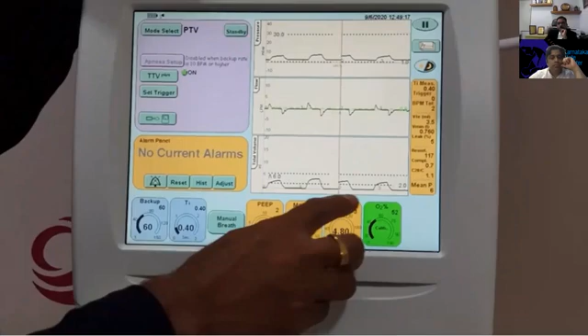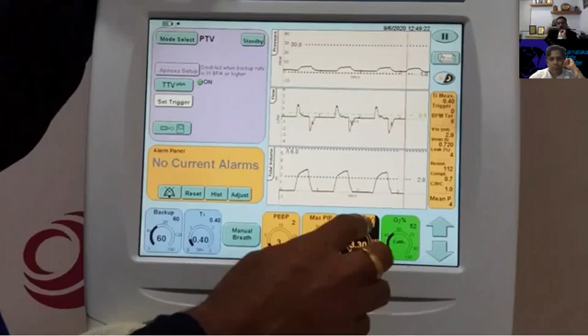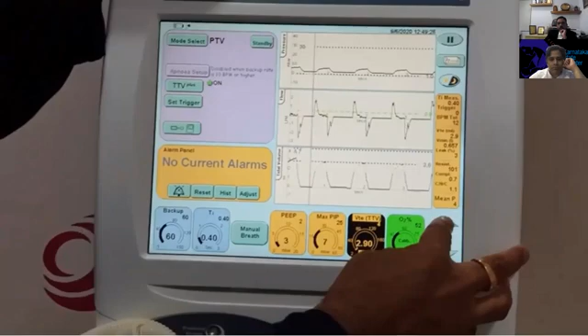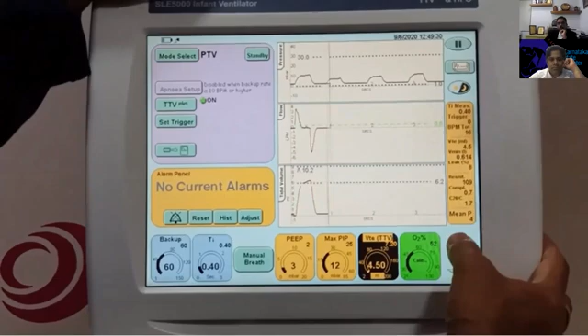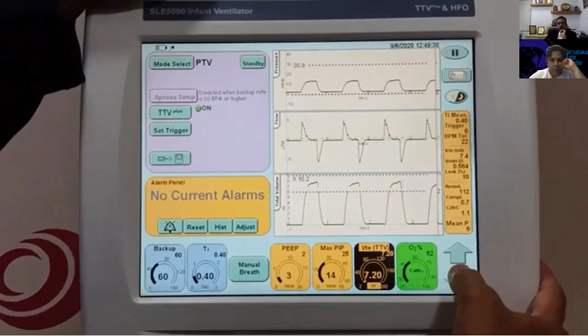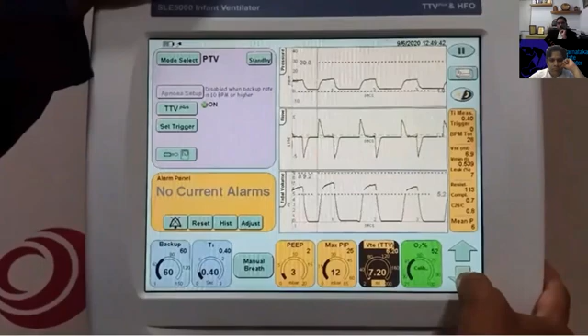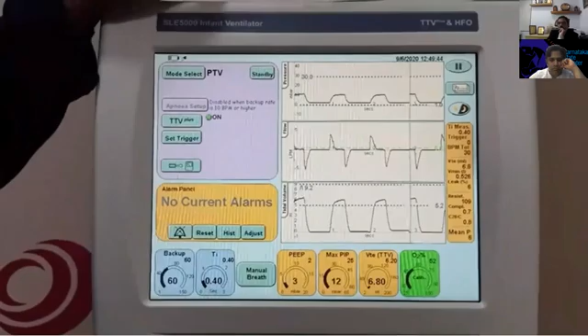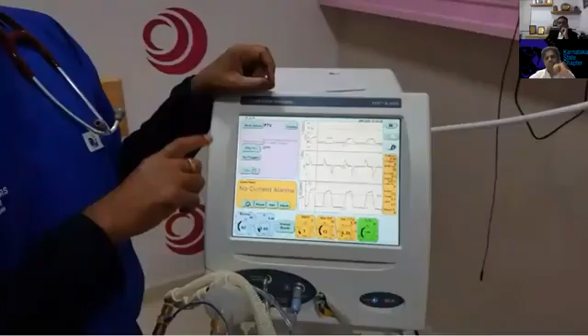Immediately, on the screen, you'll get one more parameter called the tidal volume. Now, this tidal volume you can set at around 4 ml per kg. Suppose you want to keep it at around 8, or say I will keep it around 6. Once we keep that, the ventilator will make sure that the tidal volume of 6 is achieved during every breath.